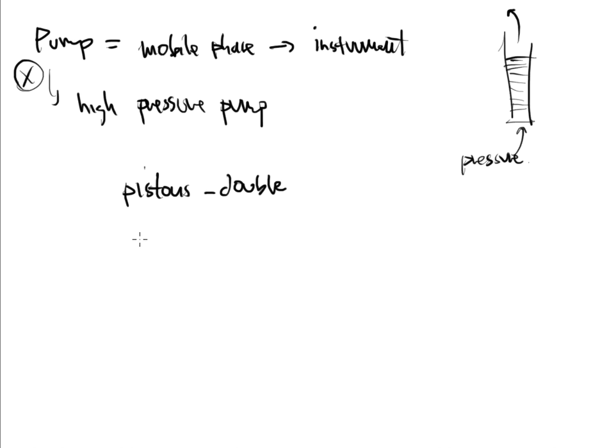As far as the pump, the material that it's made out of has to be very inert, meaning it's non-reactive. The last thing that we want is to pump a sample through and that sample and the matrix maybe react with the materials that the pump is made of. We don't want that. The same thing happens with our mobile phases. This pump is going to see the mobile phase all the time. The last thing you want is for that mobile phase to react with the pump and start to degrade it. So it's very important for the pump to be made out of pretty stable material that is very non-reactive, very inert, that withstands maybe acidity or alkalinity in the mobile phases or in your sample. Not only that, but all of the pieces and parts that make up the pump have to be inert as well.